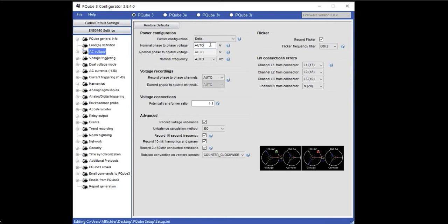Do we know the nominal voltage for our delta circuit? The PQube checks all standard voltages. If you have a different one in between, you would want to insert it here. As we run 480 here in US, we're going to put 480 there. There is no phase to neutral voltage here. It's being grayed out because I selected delta. Also in the voltage recordings, the phase to neutral channels have been grayed out because they won't be recorded, because there is no phase to neutral in delta.